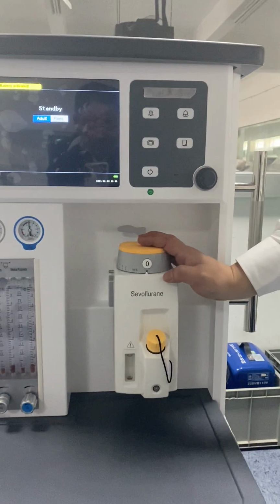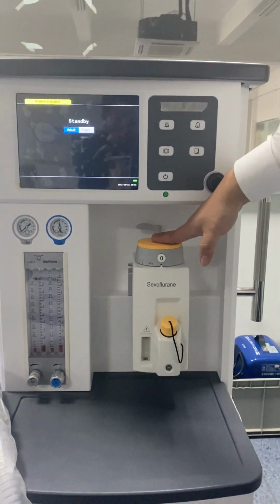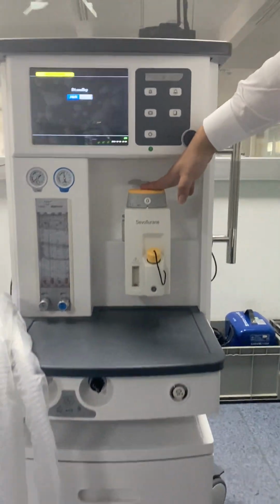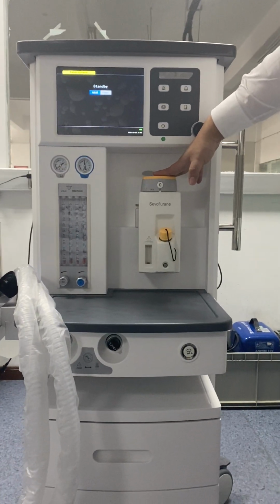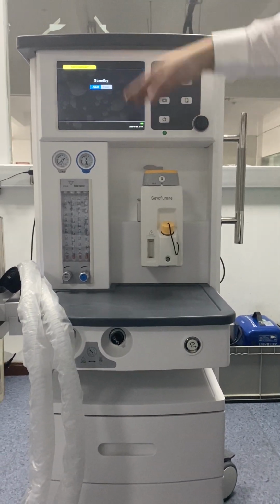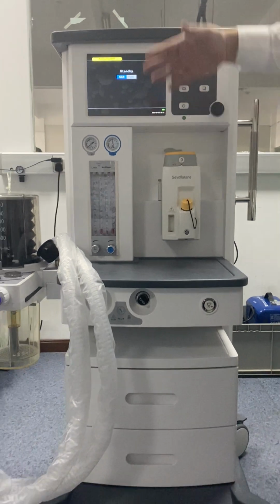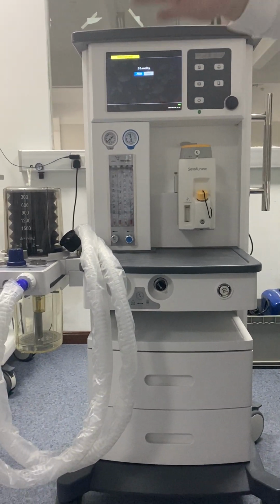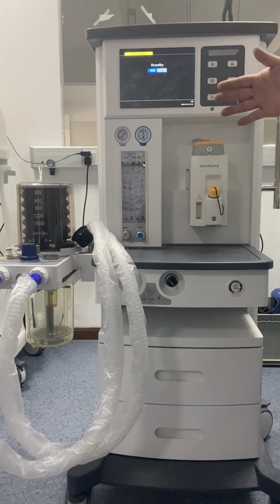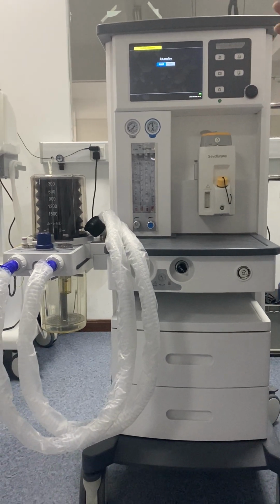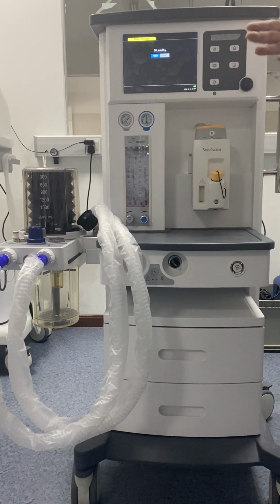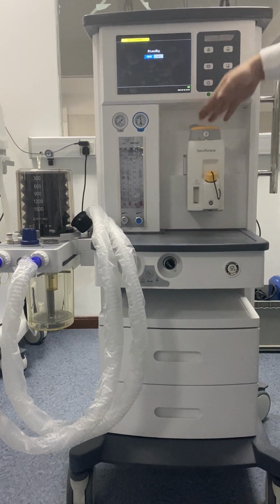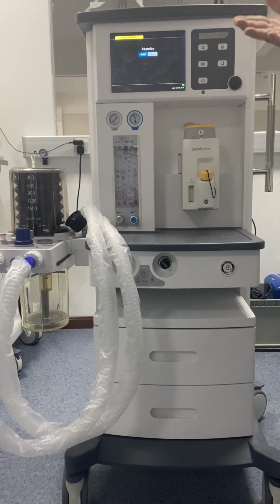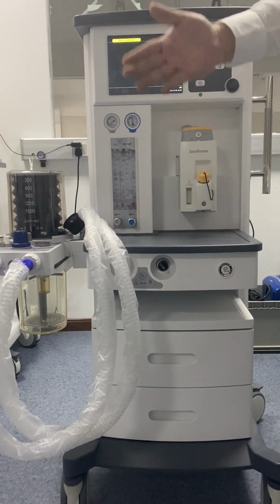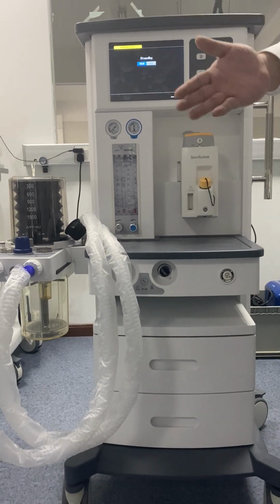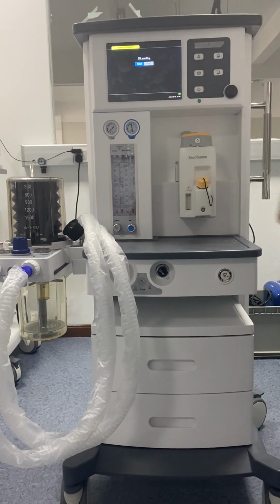Also, our vaporizer has automatic pressure, flow, and temperature leakage compensation. Because we know the whole pipeline of the anesthesia machine, from the gas source finally to the patient mask, is actually a long way, of course there must be many places for leakage. So if the vaporizer has automatic leakage compensation, it can always ensure that at the patient end, the patient always gets what the doctors want them to get.